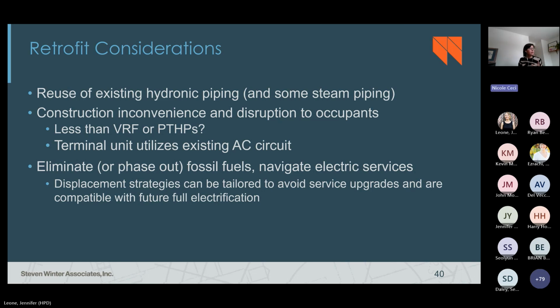So I wanted to call out that this system also works in new construction applications. It also works in retrofit applications. The terminal units that we propose tend to have the same flow rate as a typical baseboard or other hydronic terminal unit, meaning that existing hydronic distribution networks are often right-sized for use in this application as well. And you can also even reuse steam piping in many cases to convert it to hydronic application for this use. So if that steam piping is sized okay, it's usually reusable for hydronics.